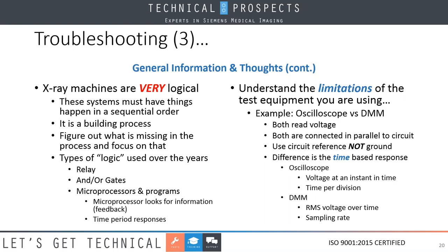Some other things that I have found in my years of experience here is understanding the limitations of your test equipment. For example here, let's look at the oscilloscope and digital multimeter that I've been talking about. We know they both read voltage because on our digital multimeters, we select the auto voltage, either AC or DC. But on the oscilloscope, you have a volts per division knob. So you're setting it, all right? When we connect these devices, they're connected in parallel to the circuit. That's important for us to realize because of the laws associated with parallel circuits. All right. Again, as I emphasized earlier, we have to use circuit reference, not ground.